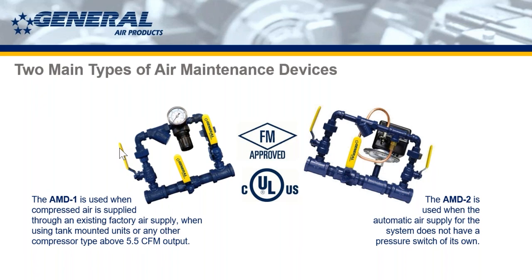So the AMD1 is used when compressed air is supplied through existing factory air supply, when there's a tank mounted unit, or when you have a flow of greater than 5.5 CFM coming from your air compressor. An air maintenance device, or AMD2, is used when the air supply device, like the compressor that you have, does not have a pressure switch of its own. So this would be the pressure switch in that instance.